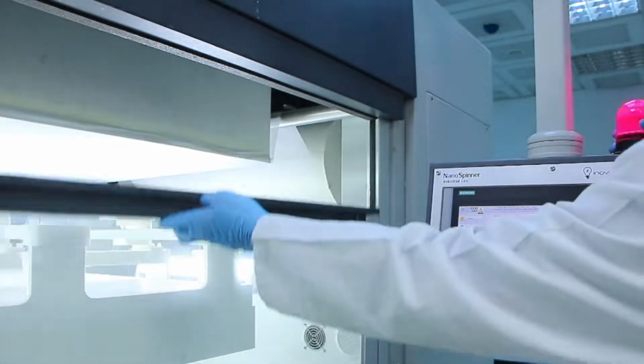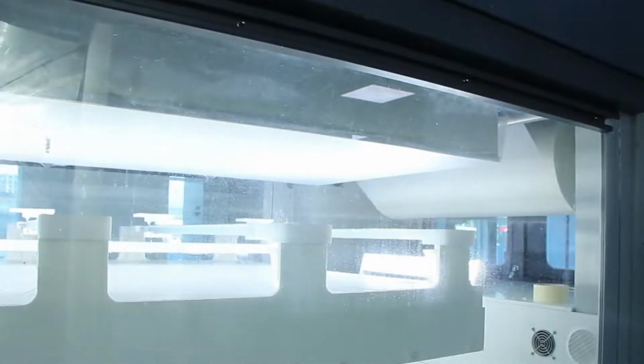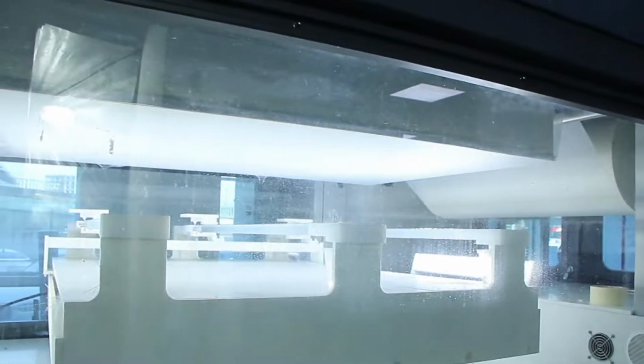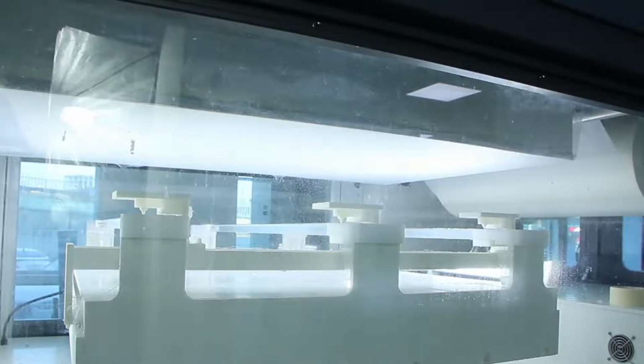It'll continue basically indicating that the door is open. There's external influence on the ambience inside, so please close the door. So there's some precaution that you have, some options you have here, just to be sure. Let me turn off the humidity again. I wanted to stay at around 34%.